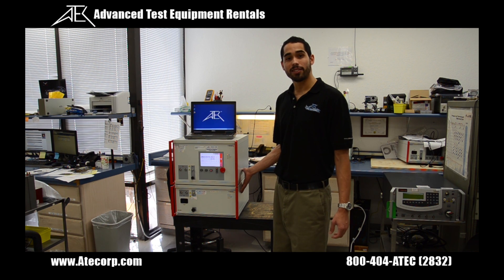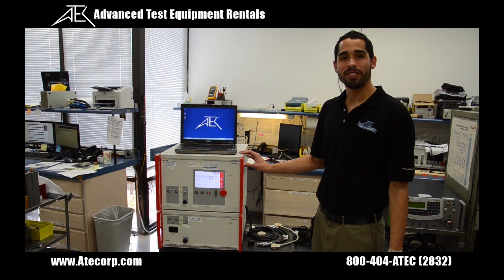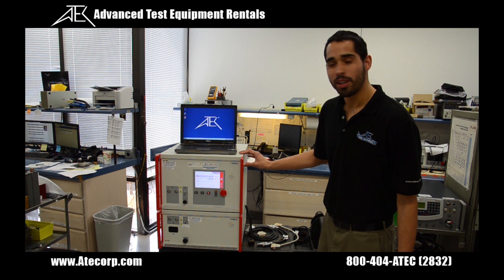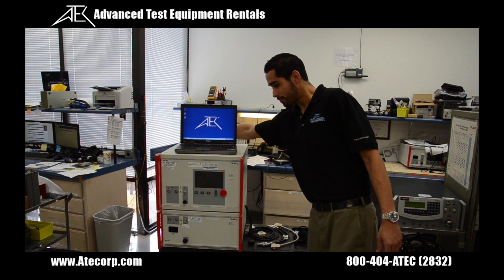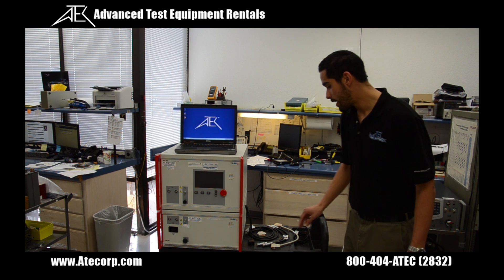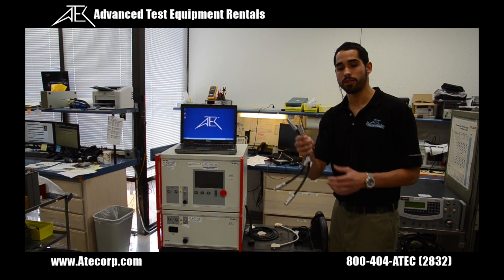We also have a single phase 16 amp CDN. The first thing I'm going to do is power off the mainframe by flipping the switch in the back. It's going to shut down. Next, I'm going to connect the two high voltage interconnect cables off the front panel.